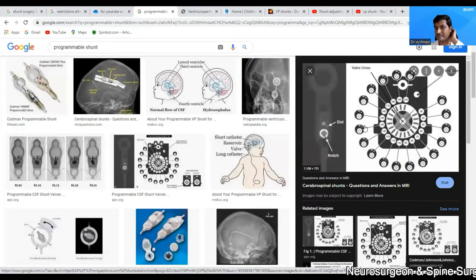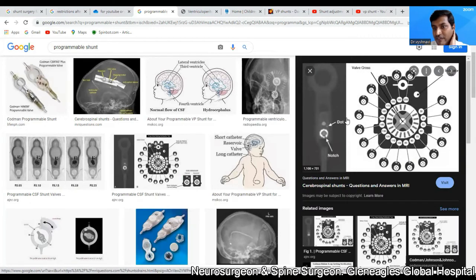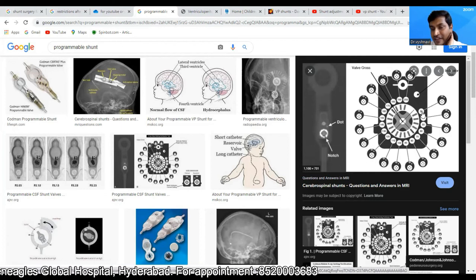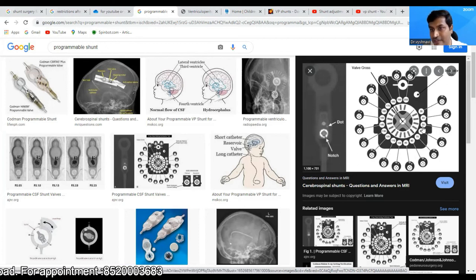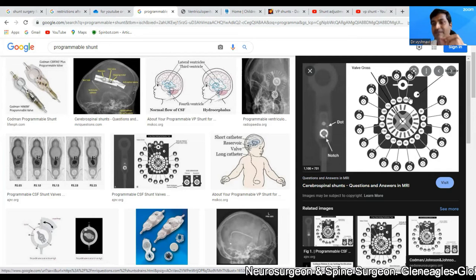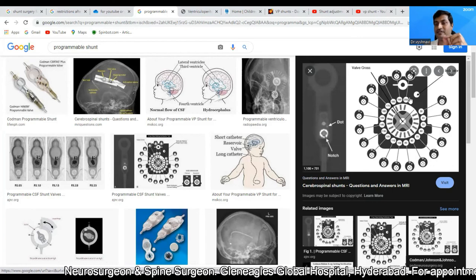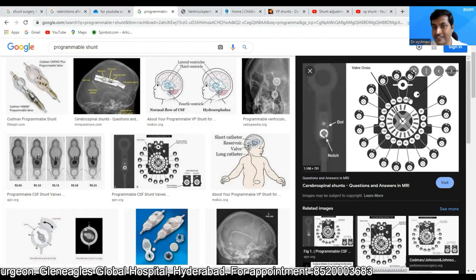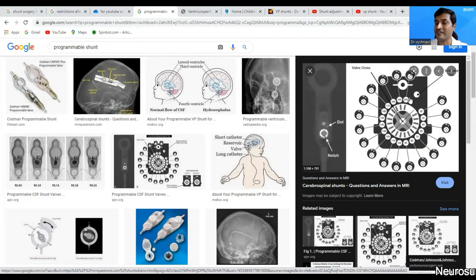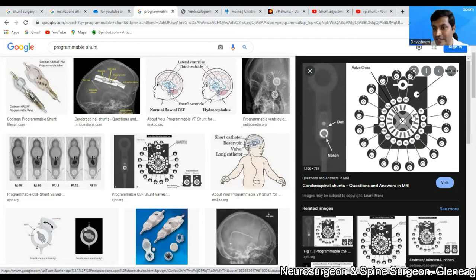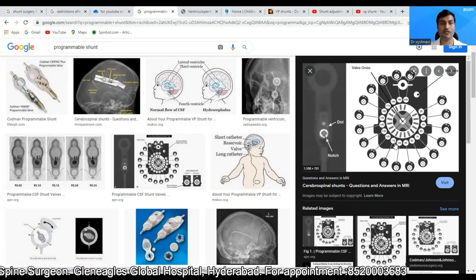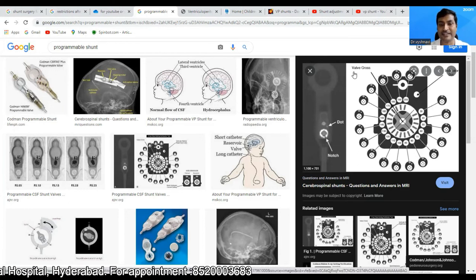This is the valve after implantation. The pressure within the valve can be set at 30, 40, 50, 60, 70, 80, 90 up to 200 mmH2O. You can pinpoint and adjust the pressure without any surgery, and the adjustment hardly takes five minutes. If the shunt is over-draining we increase the pressure higher; if it is under-draining we decrease the pressure lower.